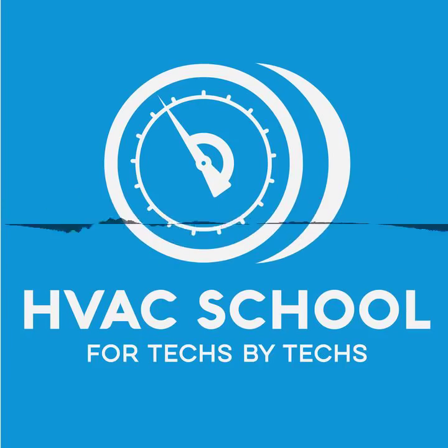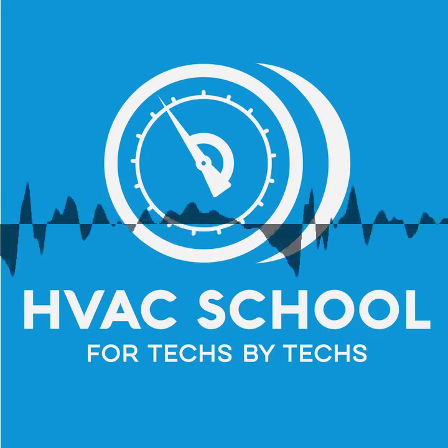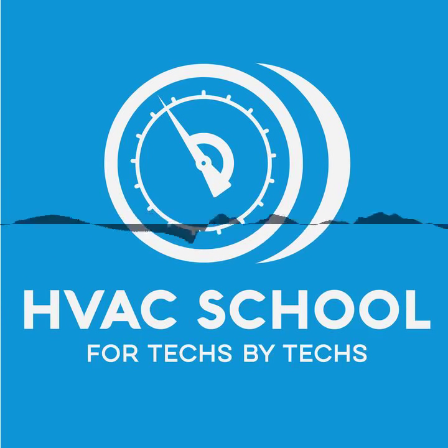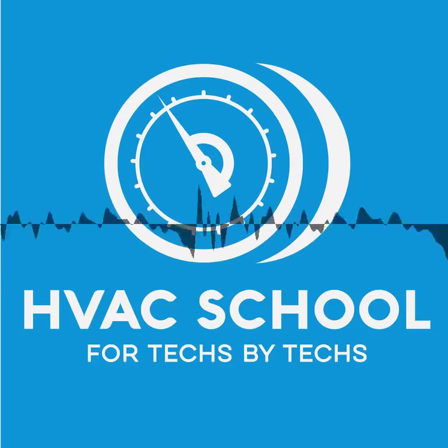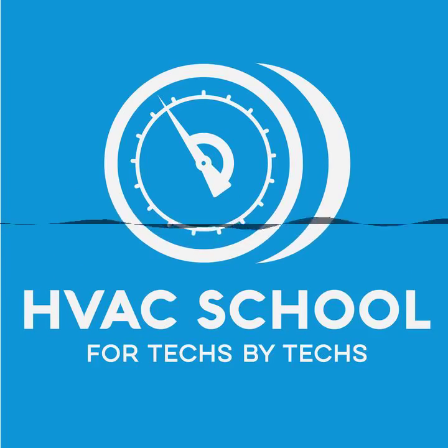So let's talk about what affects delta T, because this is practical. Anything that reduces equipment capacity can also reduce delta T, but that's not the only thing. High airflow can also reduce delta T, as can higher than normal relative humidity in the return airstream. So high relative humidity can cause a low delta T. Low capacity has an enormous list of possible causes: compressors not pumping properly, undercharge, overcharge, expansion valve issues. There are all kinds of different challenges that can cause low capacity. And then also high airflow. If a system is producing more than its target airflow, that will also reduce the delta T. And again, delta T is just the difference between air coming in the return and air going out the supply.